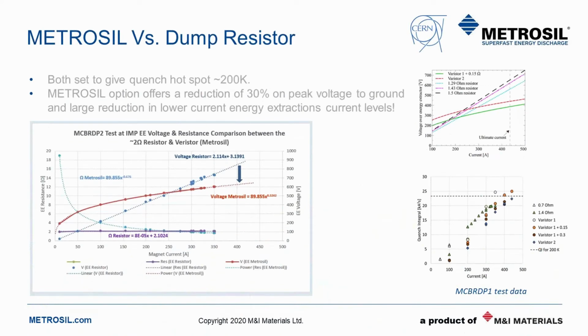We've now tested METROSIL on a number of different magnets, and we're in the process of optimizing this to control the hotspot temperatures within the magnet to around a maximum of 200 Kelvin, and also reduce the voltage to ground. On this larger plot on the left hand side, the x-axis is operating current, and the vertical axes are both resistance on the left hand side and voltage on the right. The blue angled dotted line is the performance of the resistor, and the red curved line is the METROSIL.